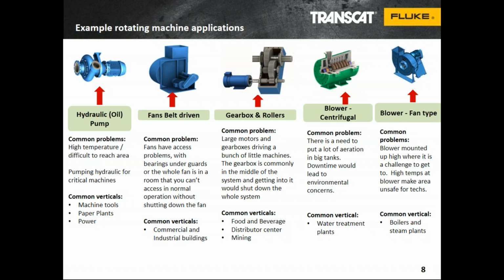Same thing with these belt-driven fans. A lot of these belt-driven fans, the bearings are behind guards and we can't get to them, so access makes it very tough without shutting the machine down. This is in almost every application - every plant you can think of is going to have some type of exhaust or supply fans, and we're having trouble getting to those without removing guards, which makes it unsafe. So by putting remote sensors in there, we can prevent that safety issue.